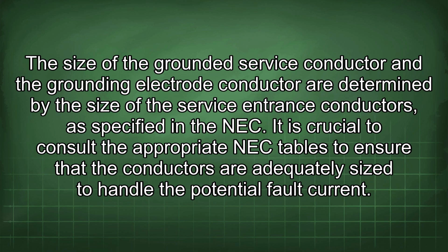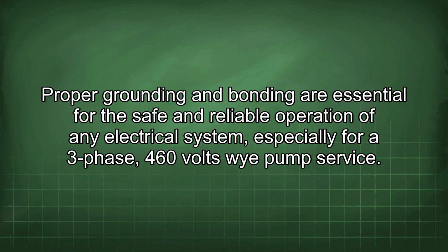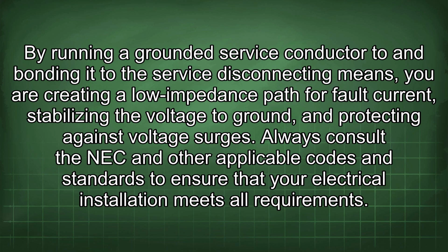It is crucial to consult the appropriate NEC tables to ensure that the conductors are adequately sized to handle the potential fault current. Proper grounding and bonding are essential for the safe and reliable operation of any electrical system, especially for a three-phase 460 volts Y pump service. By running a grounded service conductor to and bonding it to the service disconnecting means, you are creating a low impedance path for fault current, stabilizing the voltage to ground, and protecting against voltage surges.